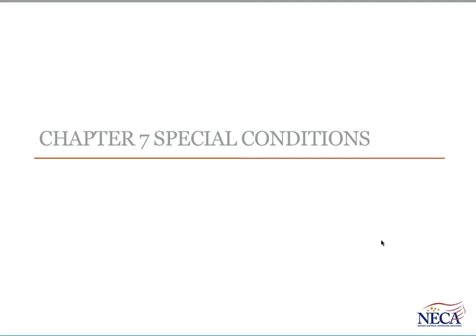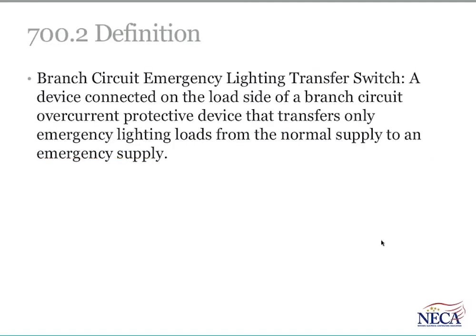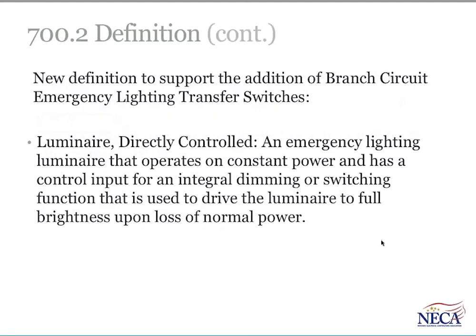Chapter 7 in the NEC covers special conditions. I got a change or two here, and then we cover Chapter 8 and open it up to some questions. First of all, a new definition: branch circuit emergency lighting transfer switch is a device connected on the load side of the branch circuit device. In other words, on the load side of a breaker, typically, it transfers only emergency lighting loads from the normal supply to an emergency circuit. We're not transferring a feeder in this case, it's just a branch circuit.